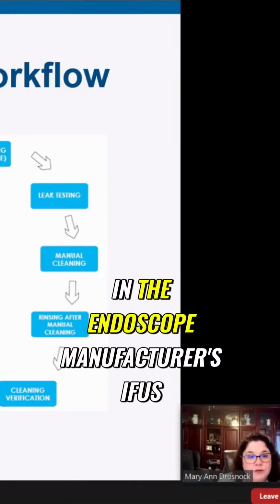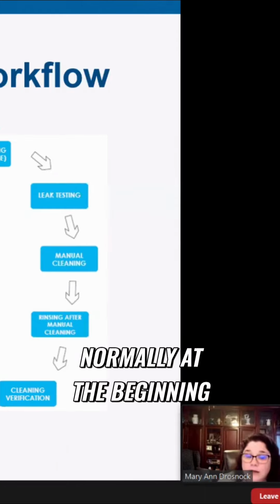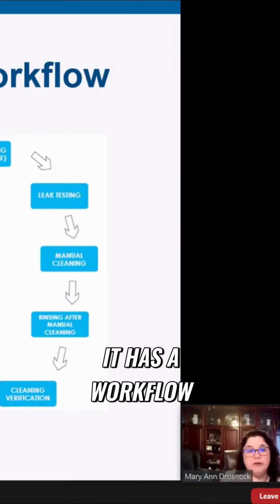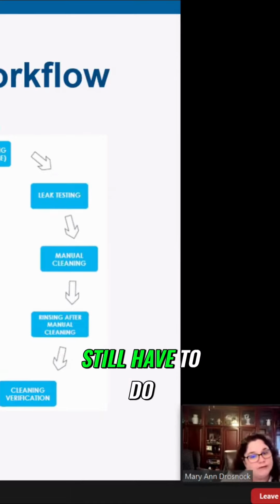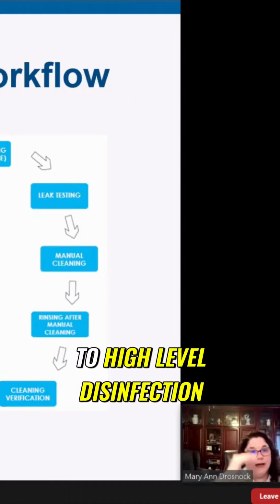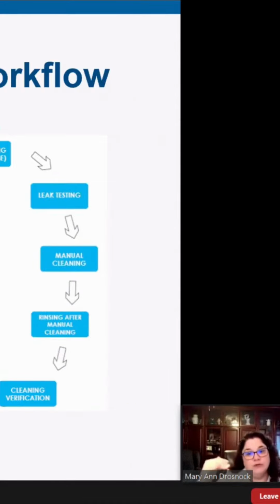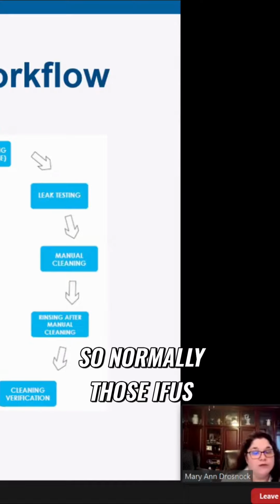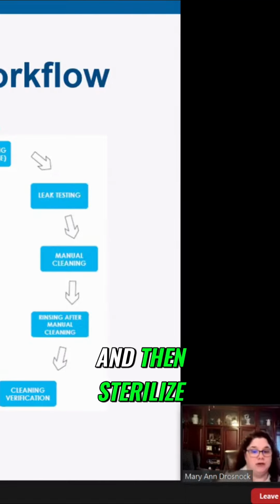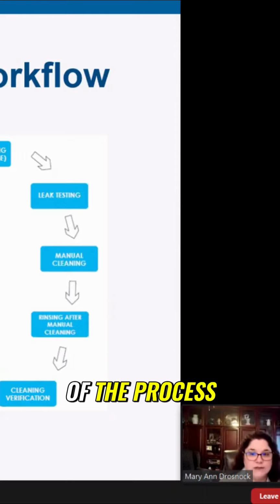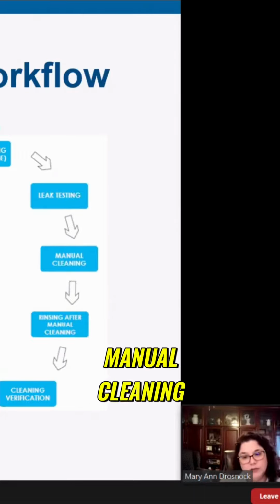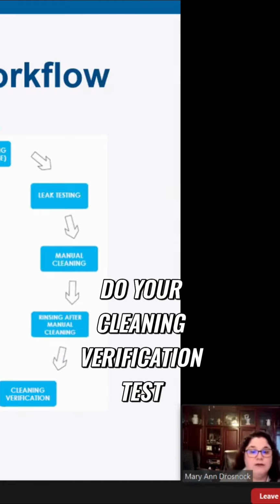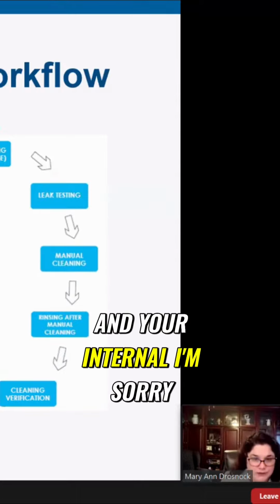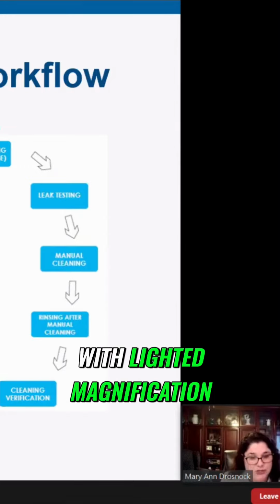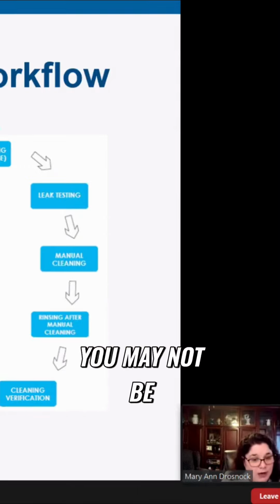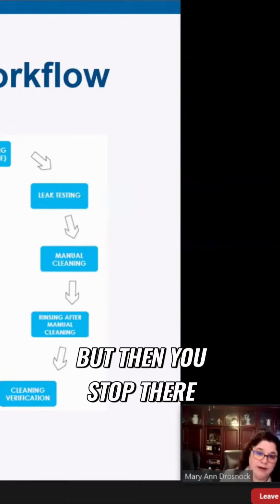And if you look in the endoscope manufacturer's IFUs, normally at the beginning of that reprocessing manual, it has a workflow. So it tells you what steps you still have to do to get to high-level disinfection, and then what steps you have to do for sterilization. Normally those IFUs don't say you disinfect and then sterilize. You do the beginning part of the process. So you do your point of use treatment, leak testing, manual cleaning, rinsing. Then you're going to do your cleaning verification test and your external inspection with lighted magnification. You may be using a borescope at this point. You may not be. But then you stop there.